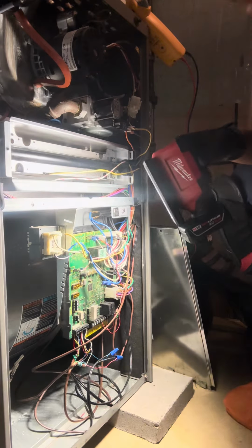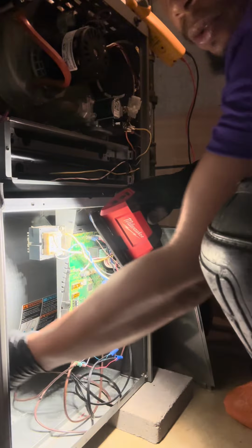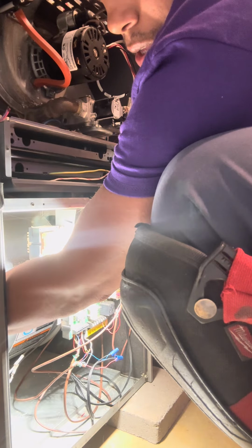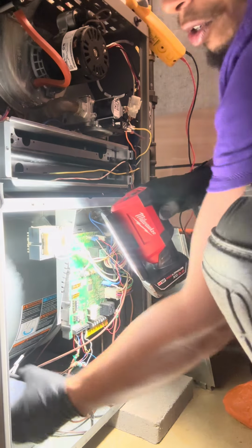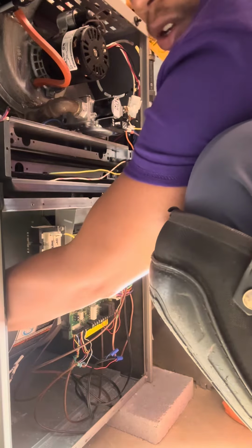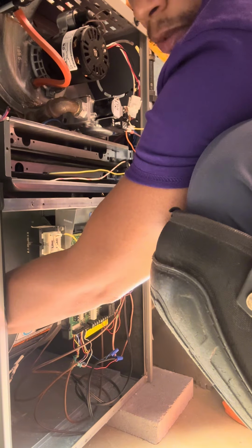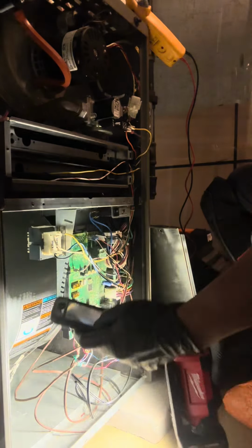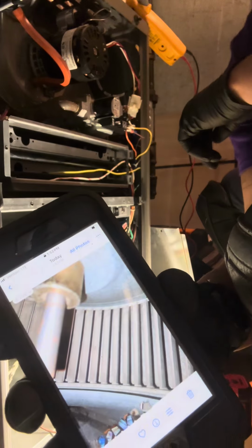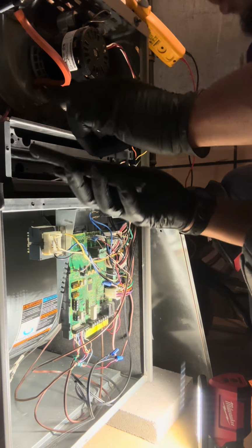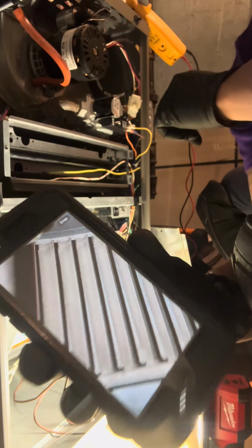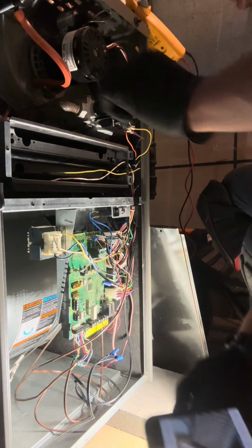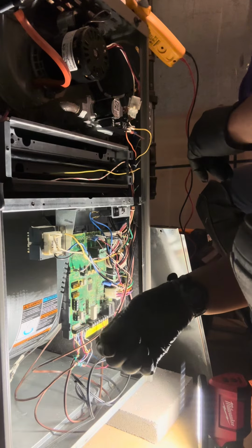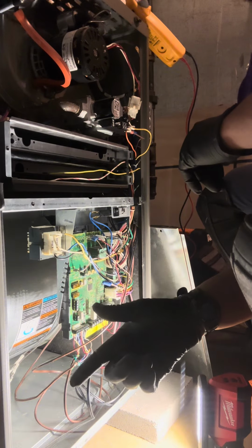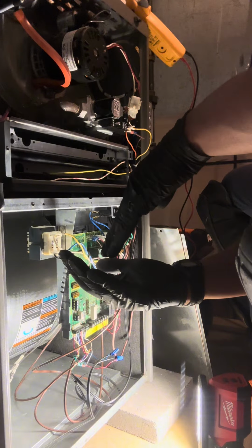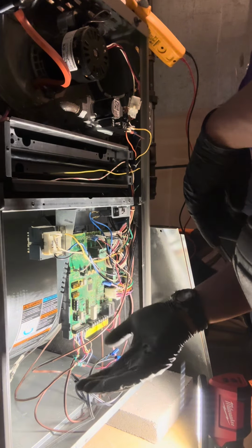Next thing I'm going to do is I'm going to get my hand in here. I'm going to snap a photo of your blower wheel. I want to make sure that it has no corrosion on it or any buildup of dirt. That's the blower wheel. So looking at that, that looks pretty good. Let's zoom in, make sure there's absolutely no dirt on there. A small amount of dirt is okay, but the more dirt that builds up on that blower wheel, it kills the efficiency and it kills the airflow, because it takes up the surface area that the blower wheel needs in order to throw the air.